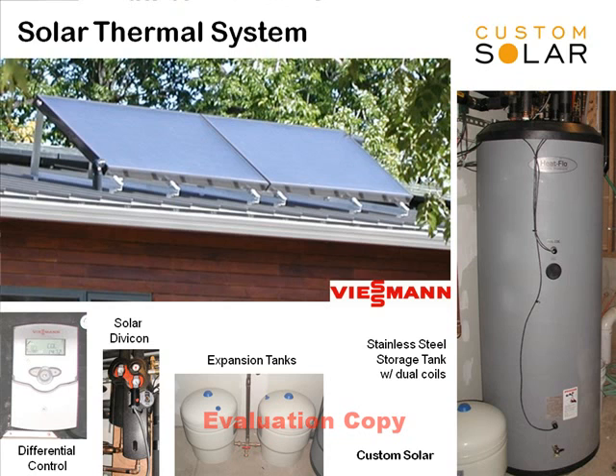Custom Solar of Boulder, Colorado installed a top-of-the-line solar thermal system using Viessmann collectors, pump station, and differential control, and a propylene glycol approach to freeze protection. Heated water is stored in a stainless steel solar storage tank. Copper coil heat exchangers in the solar storage tank permit heated water to be sent to the domestic hot water system, the radiant floor heating system, as well as to the geothermal ground loop heat exchanger in a sequence called solar banking.